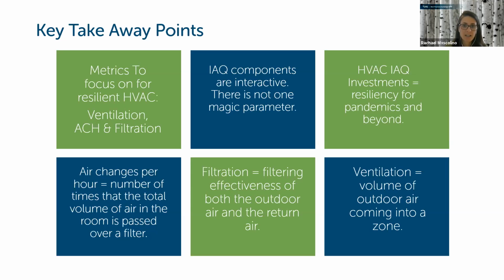So it depends on the thickness of the filter that they're transitioning to, and what's available for an easy retrofit. Something to keep in mind is that because you've got a filter now that's capturing really, really small particles, that filter is going to get loaded up more quickly. So with all of the pollens and the stuff in the air, you may need to do an extra filter change to make sure you're still getting the airflow that you need through that filter.